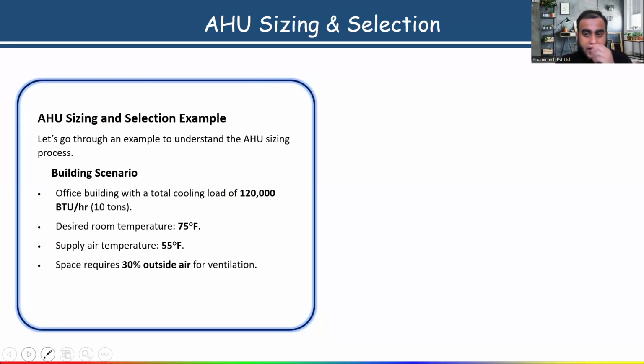Here one point is given: space requires 30% outside air. Suppose the air which you are taking back from the room, the return air, we only have to clean it, then cool it, and then supply it. But we are also taking the outside air, fresh air. So here they have given space requires 30% outside air.